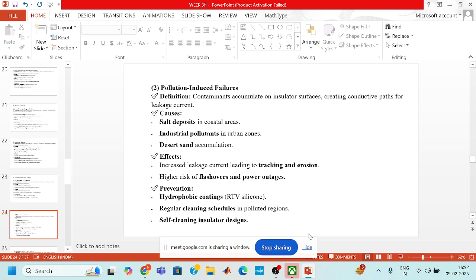Now second is pollution induced failures. Contaminants accumulate on insulator surfaces, which creates conductive paths or leakage currents, because of salt deposits in coastal areas, industrial pollutants in urban zones, and sand accumulation in deserts. All this increases leakage current, which leads to tracking and erosion, and there will be a higher risk of flashovers and power outages. So we can use hydrophobic coatings like RTV silicone, a regular cleaning schedule in pollutant regions, and self-cleaning insulator design.